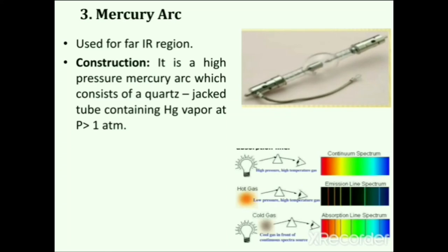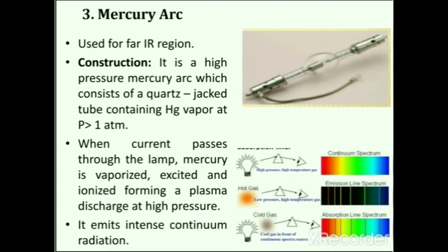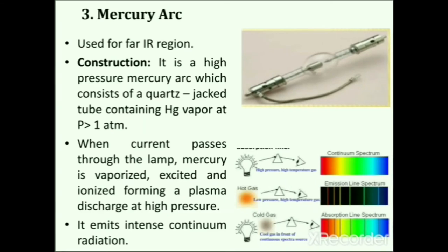Next is the mercury arc, which provides radiation in the far infrared region. It is a high-pressure mercury arc consisting of a quartz jacket tube containing mercury vapor at more than one atmospheric pressure. When current passes through the lamp, mercury is vaporized, excited and ionized, forming a plasma discharge at high pressure, emitting intense continuum radiation in the far infrared. There are generally three types of radiation spectra: continuum spectrum, emission line spectrum and absorption line spectrum. A spectral continuum occurs when the interaction of a large number of atoms, ions or molecules spreads out all the discrete emission lines so they can no longer be distinguished.